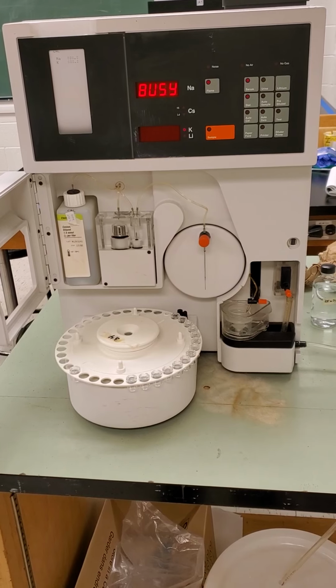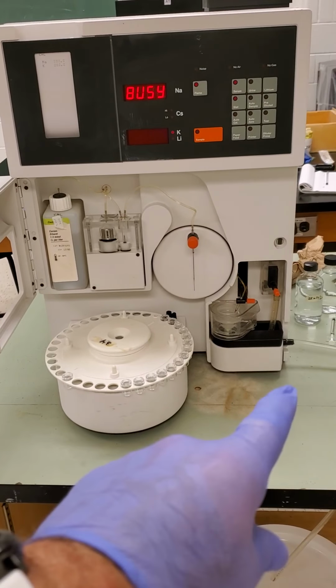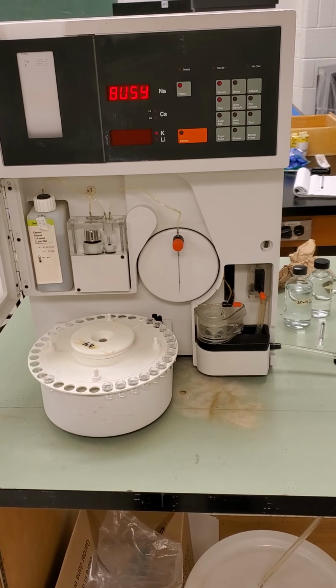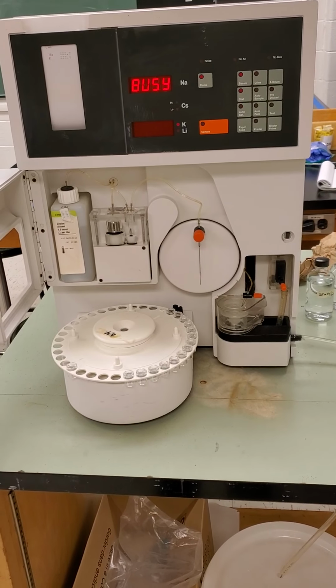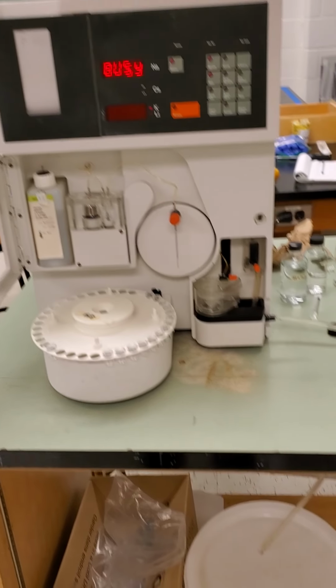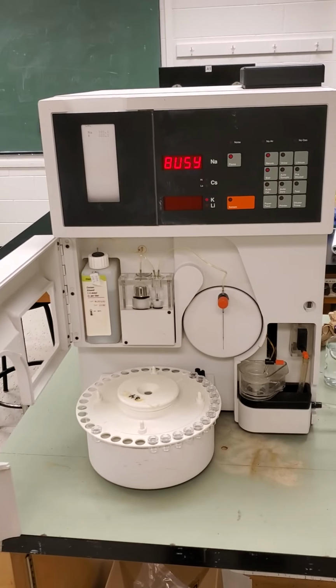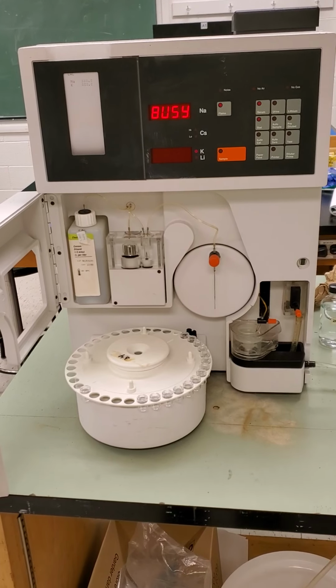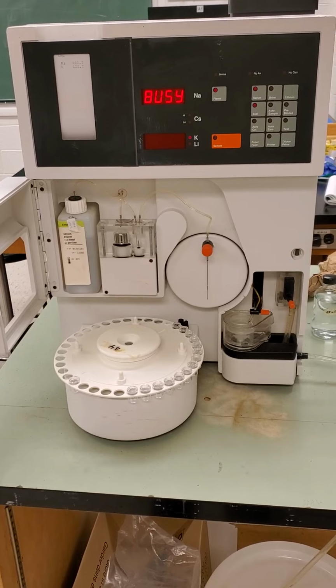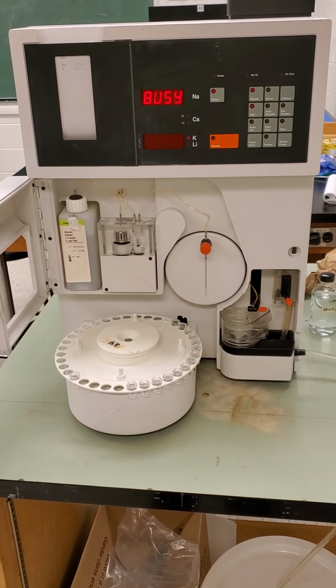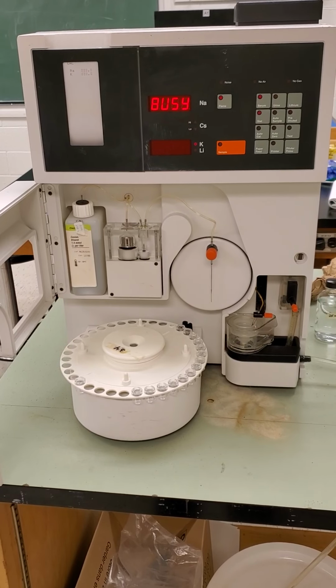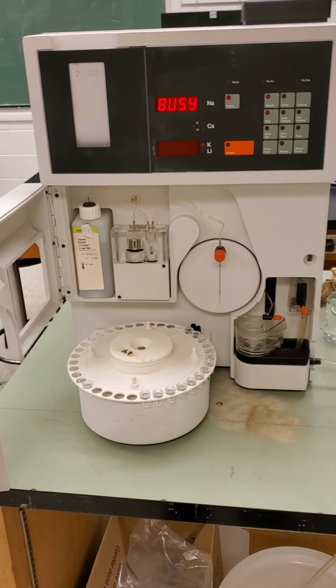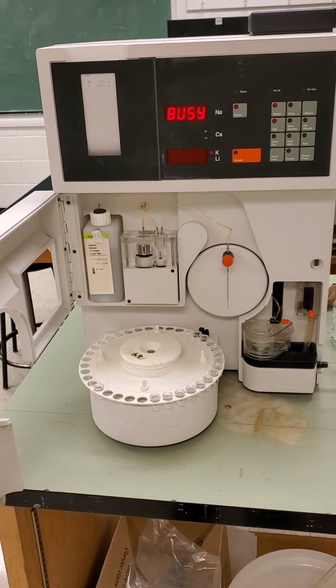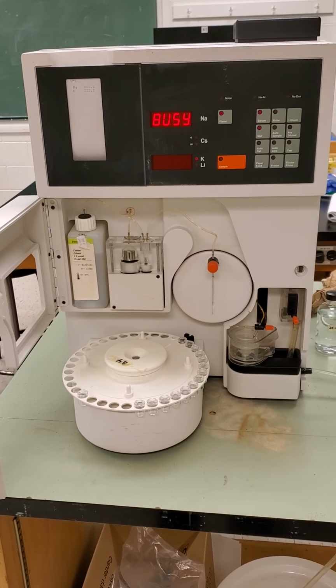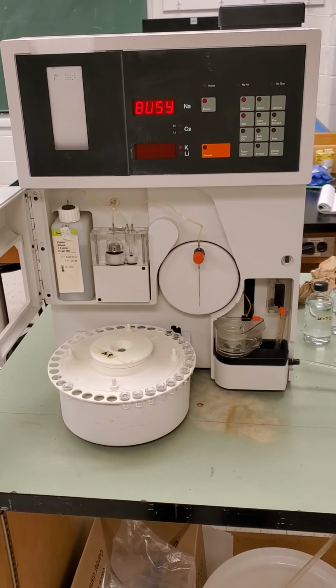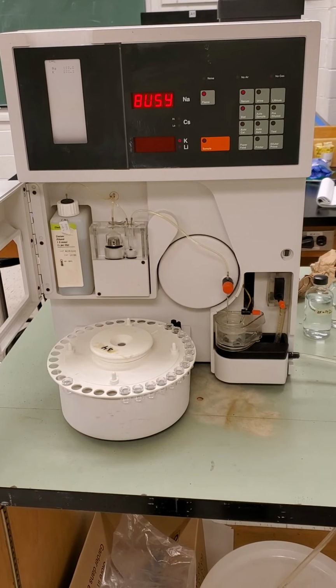So it'll take a few minutes. Sometimes it does it once or twice. You can see over on the side here some of the water that didn't make it into the burning sample chamber dropping down into a reservoir that we have underneath the flame photometer. So once it's happy that it's started up, the next thing we'll do is select urine, auto sample, and auto cal, and that will start the sampling. It'll calibrate itself and then go through and pick up all the samples and give us results.